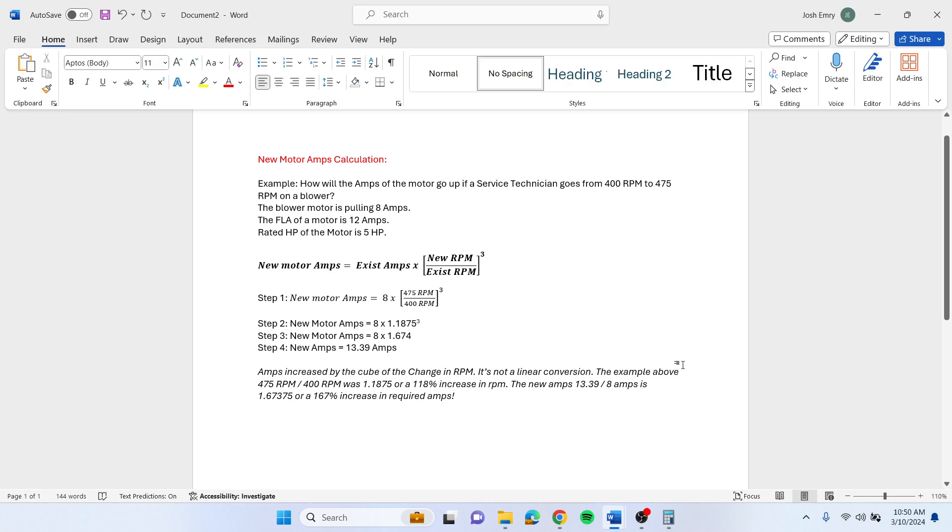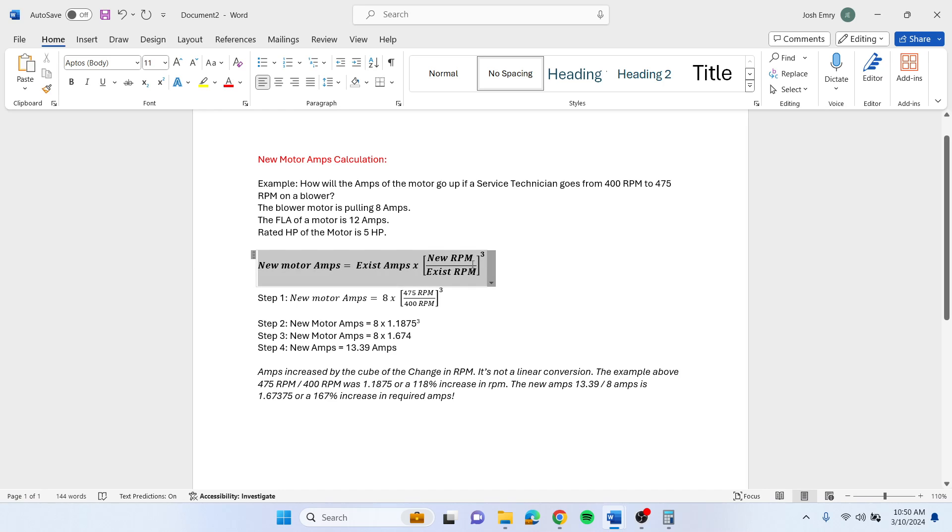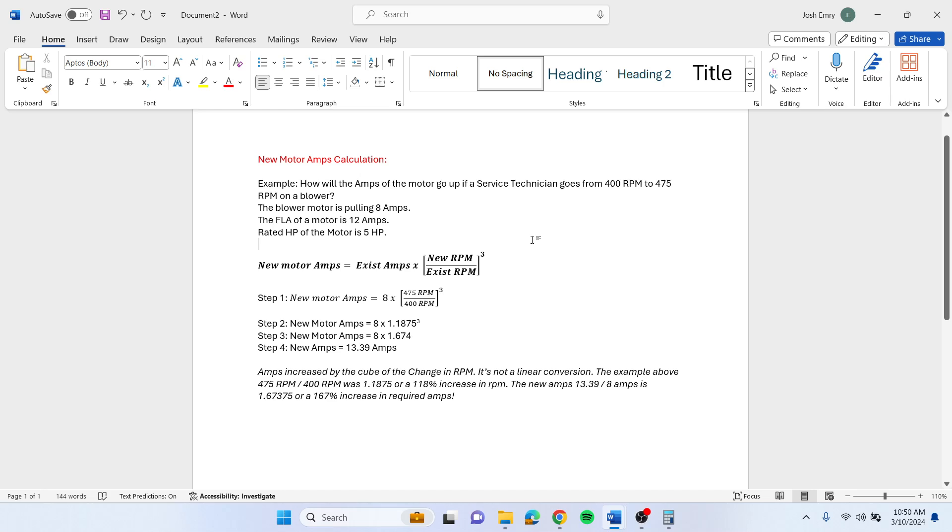Let's say you want to increase your blower RPM because you need to get more airflow. You're going to want to know what your amps are going to go up, and this equation here will work to let you know how much your amps are going to go up by changing your blower RPM.